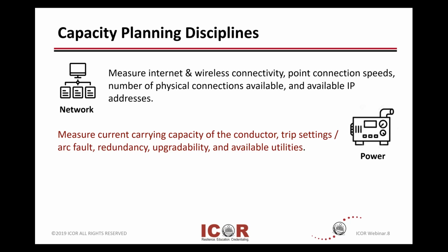Making sure also - I mentioned power, especially in data centers - you're all very familiar with critical environment backup, alternate, or conditioned power. That runs everywhere from your service entrance, making sure you have the right sized breaker capacity and feeders running through your conductors, checking your trip settings, ratings and capabilities, arc fault, redundancy and upgradability, and the ability to switch over to your backup or conditional power system.